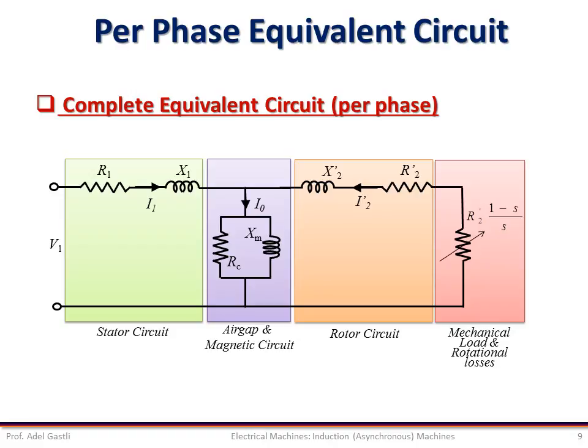For instance, if the stator winding is star-connected, since V1 in this circuit represents the phase voltage, the actual motor terminal voltage is √3 × V1. Also, the total torque is three times the per-phase torque, and the total power is three times the per-phase power.